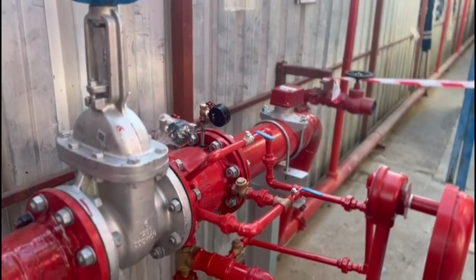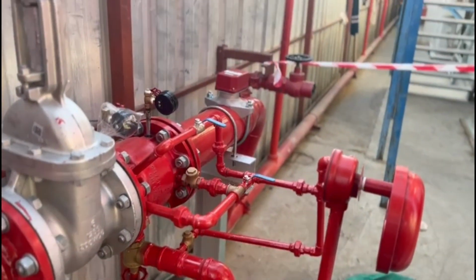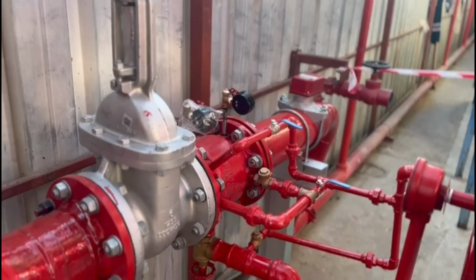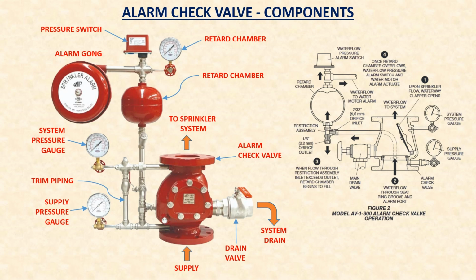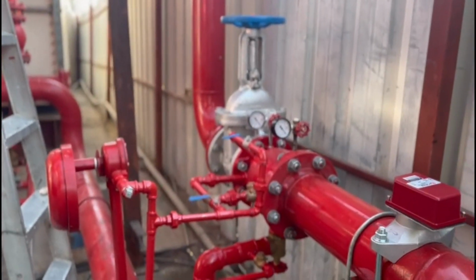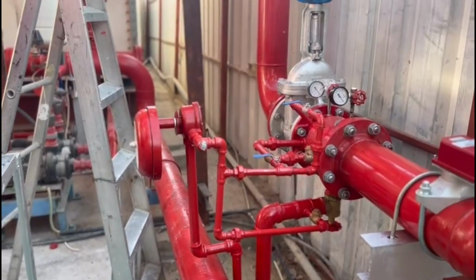To conclude, the alarm check valve is commonly used in wet pipe sprinkler systems. They are not used for standpipe systems like fire hose reels or landing valves. The alarm check valve is a vital component of a wet pipe fire sprinkler system responsible for controlling water flow, preventing backflow, and activating the alarm system when a fire is detected.